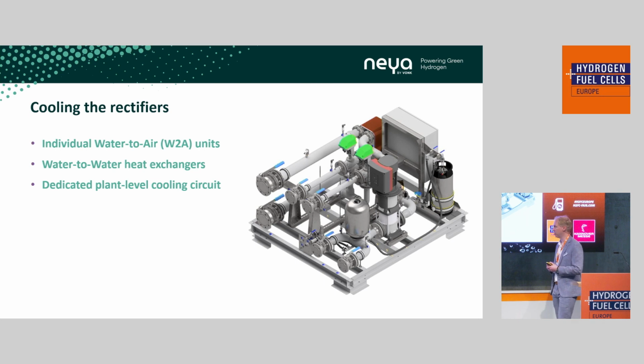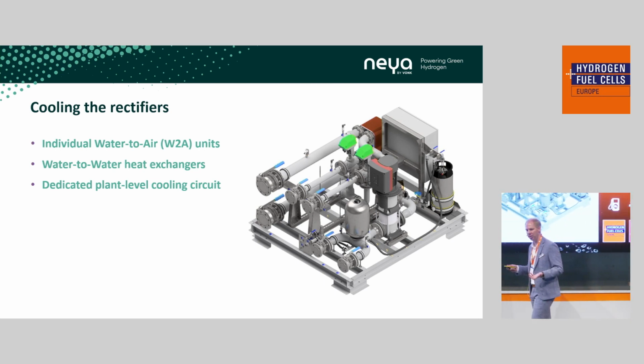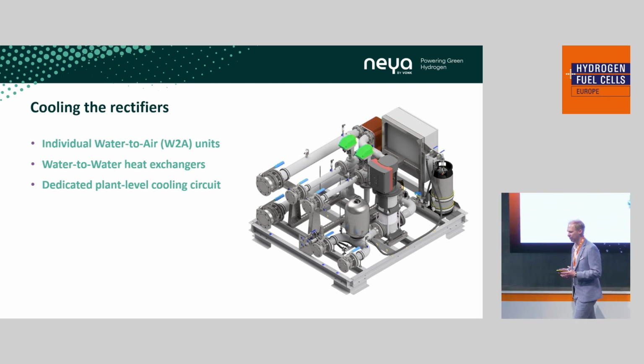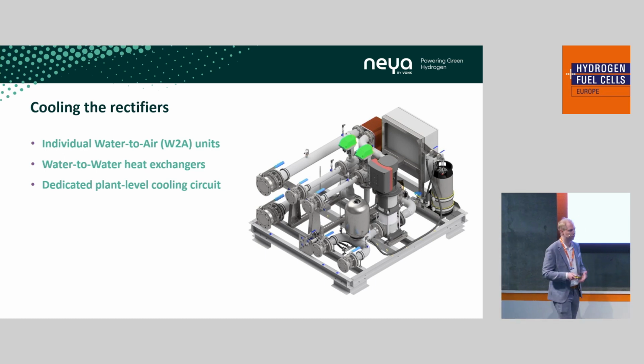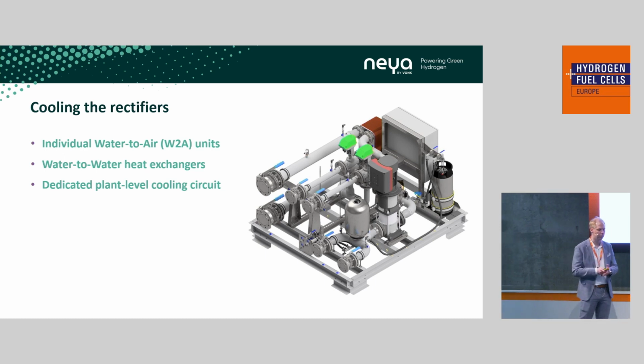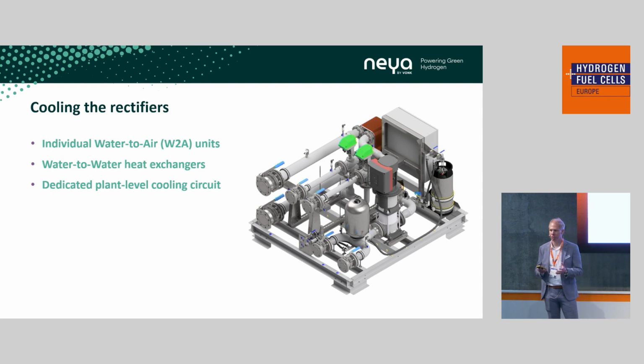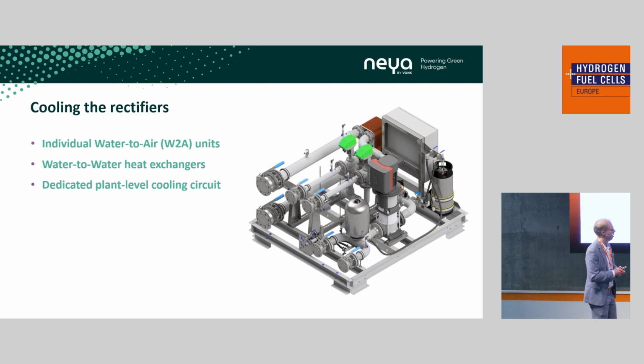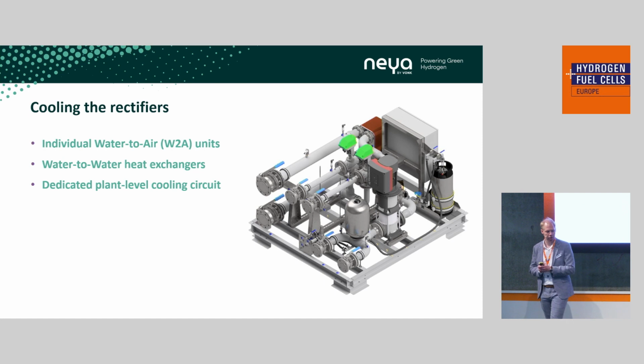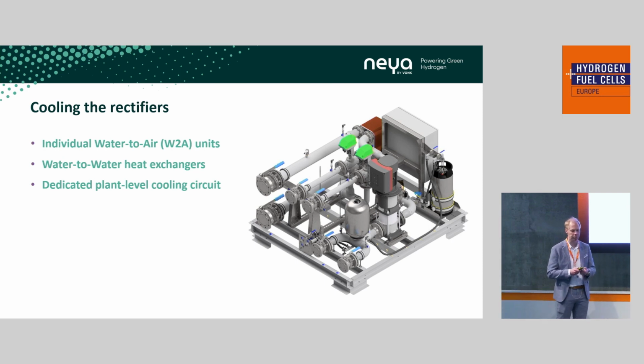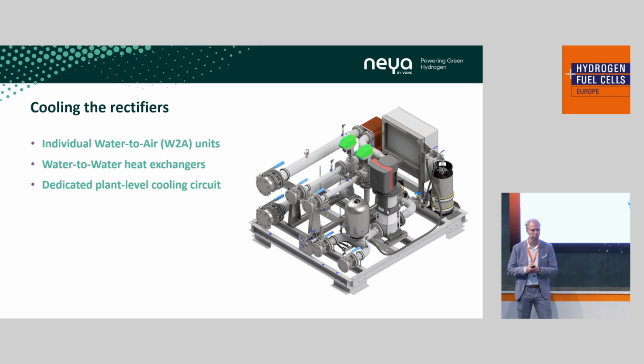Another point of attention is cooling. If you have an individual rectifier for a small project, it's not much of a topic — you just apply a cooling unit for that rectifier. But for a bigger project, you might want to connect it directly to a plant cooling system. You can use a water-to-water heat exchanger, for instance, to make this connection, giving you an independent cooling circuit for your rectifiers with specific requirements while still connecting to the plant's cooling system.